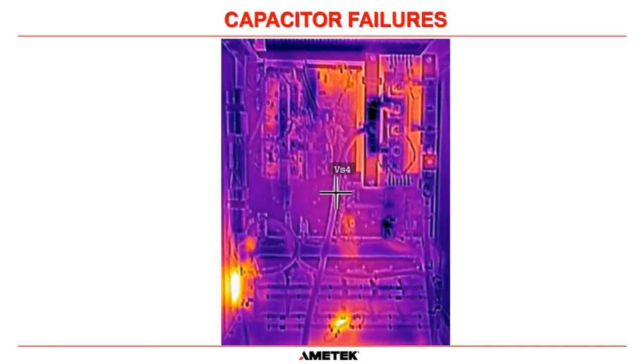Now, once again, we can do a thermal scan, which we do, and you can see in this picture here that we have a row of DC capacitors, and they are all the same temperature. You can see here that there is something that's hot. That is the discharge resistor that's connected across the DC capacitors. We know that that should be hot. It will dissipate power all the time, but we can see there are no capacitors here showing any signs of excess heat. So that's another good way to show that the capacitors are within the tolerances.